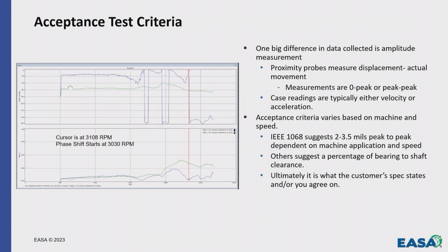So one big difference is we've talked about mils some. We're actually measuring actual movement, not just energy. So once again, if we know we've got 10 thousandths clearance in that bearing and we're at 5 mils, we're taking up half the space of that bearing with vibration. And measurements are typically 0 to peak or peak to peak. We don't use RMS when we're looking at case probe readings, I'm sorry.